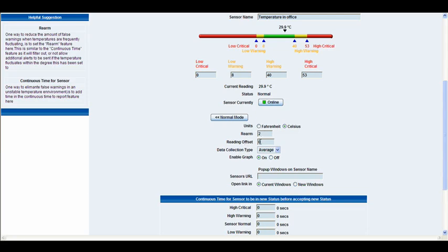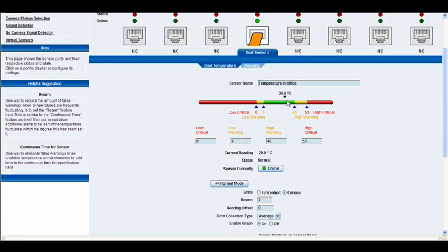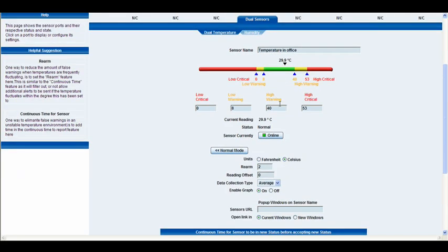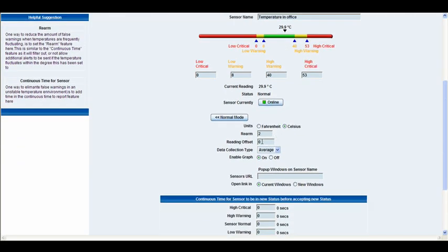Reading offset, essentially what this does is if your sensor displays 29 or 30 degrees, you can actually offset it by however many degrees you want. So if you offset it by two degrees and it displayed 30, it would actually display 32 degrees.